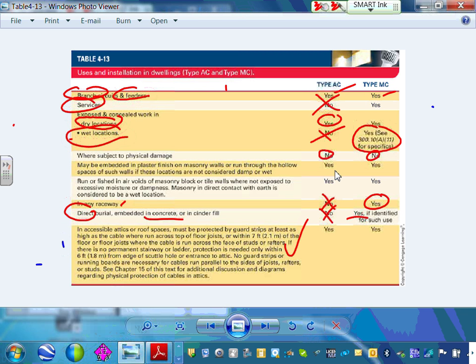Now you're going above ground in an area where Chad Kearney can drive his Suzuki right into it. What's your conduit of choice? Rigid steel, typically steel rigid, where you can drive right into it. Okay, or schedule 80. PVC schedule 80 will do you.